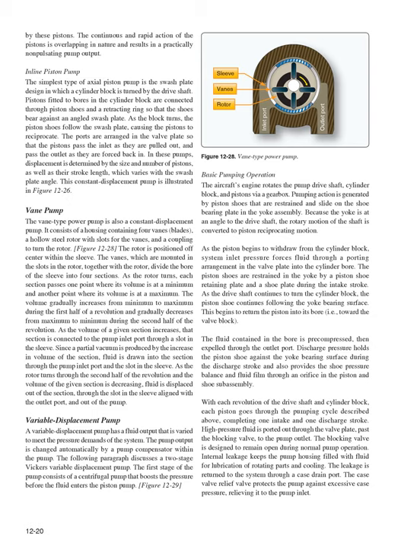With each revolution of the drive shaft and cylinder block, each piston goes through the pumping cycle described above, completing one intake and one discharge stroke. High-pressure fluid is ported out through the valve plate, past the blocking valve, to the pump outlet. The blocking valve is designed to remain open during normal pump operation.